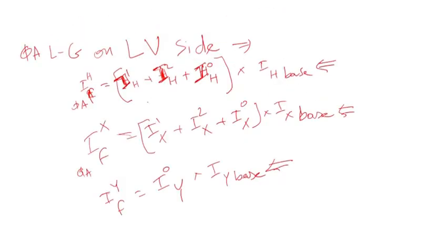So as you see here, for the high voltage, basically we sum up to get the A phase current due to a low voltage line to ground fault with some of the positive, negative, and zero sequence. The same thing for the low voltage winding, but for the tertiary one or the delta, only zero sequence will flow. That's why I did not sum up I0, I1, I2. So that's important to know.